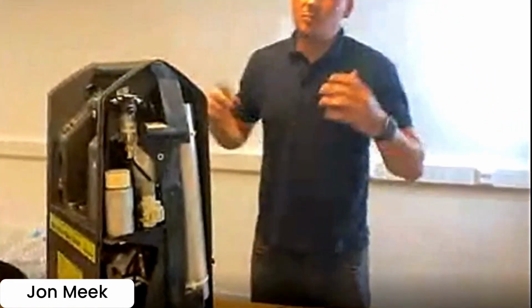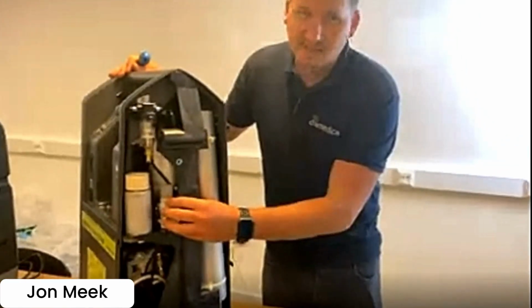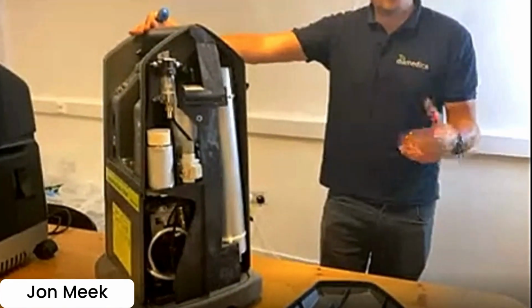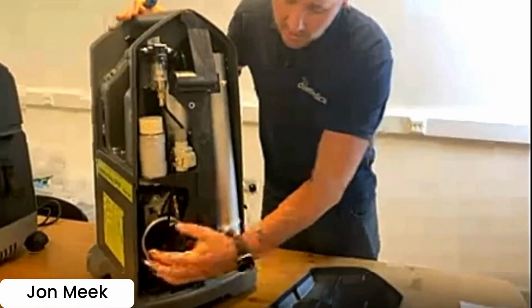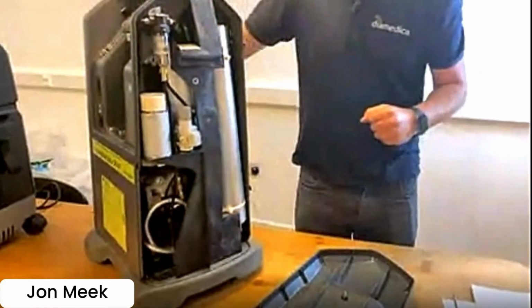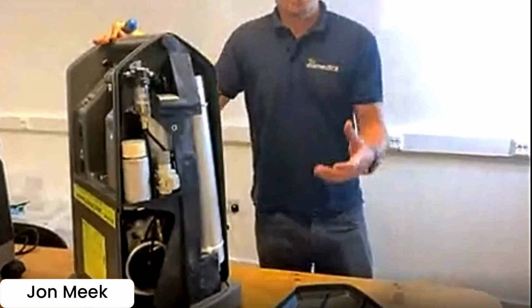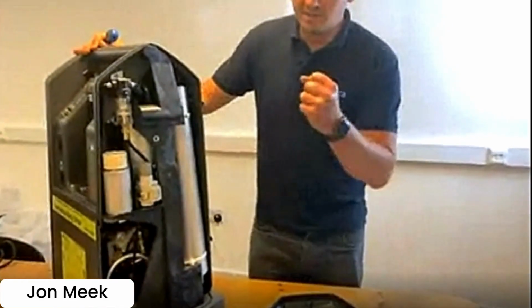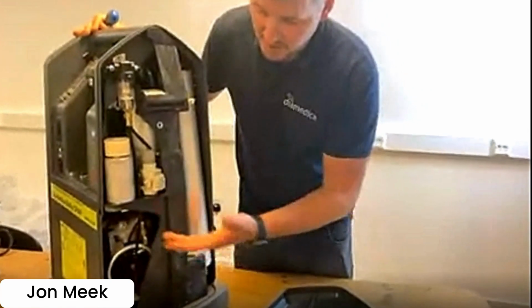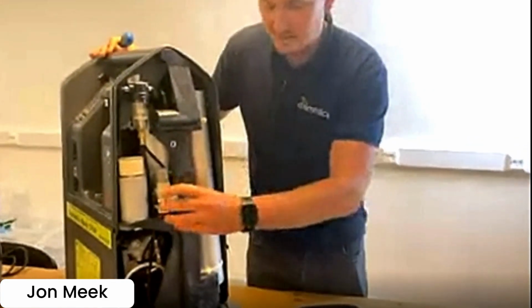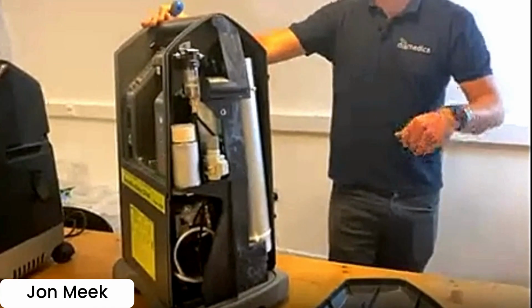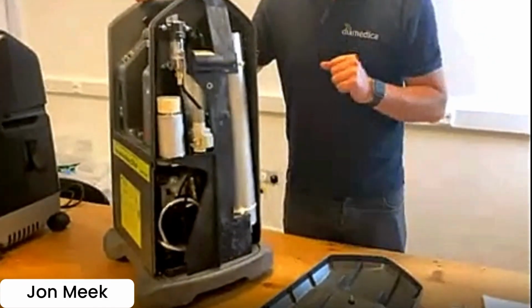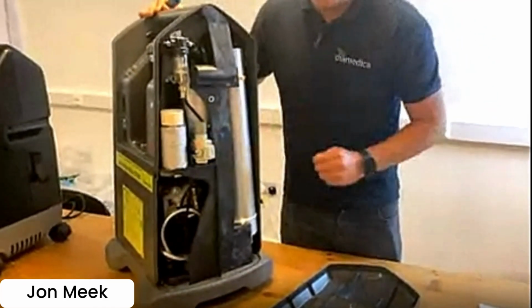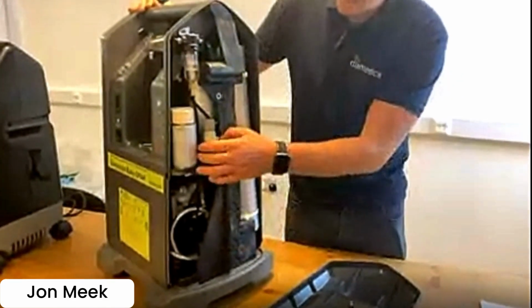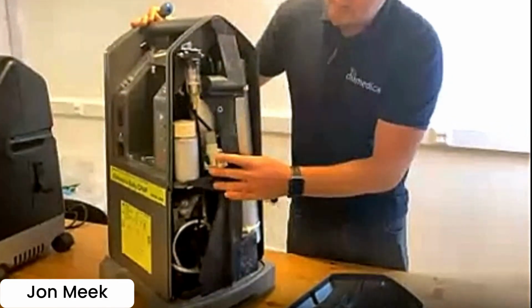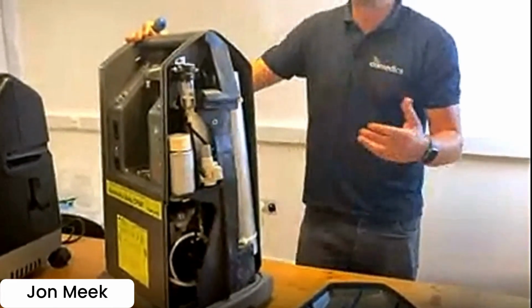So on the first model, we had different regulators. We want to regulate and control the flow and pressure. So we're using the compressor inside the CPAP, which is used to generate the oxygen through the sieve beds. We're actually taking a tap off from the compressor, but it's going through a regulator. This is the latest version of the regulator to maintain a steady flow of up to 10 litres a minute of oxygen.